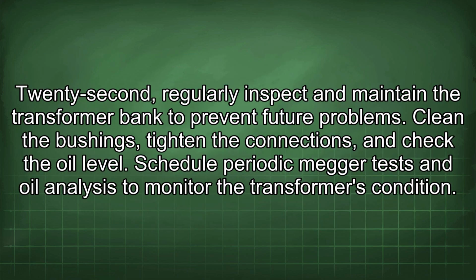22nd, regularly inspect and maintain the transformer bank to prevent future problems. Clean the bushings, tighten the connections, and check the oil level. Schedule periodic megger tests and oil analysis to monitor the transformer's condition.